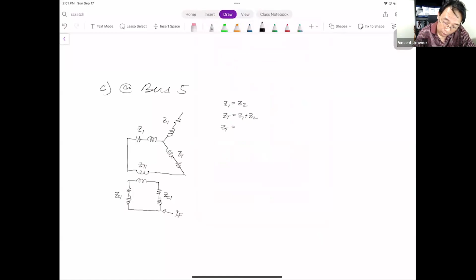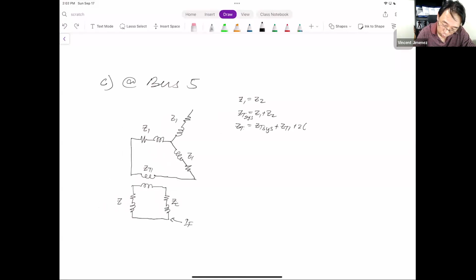Base naman sa formula natin, if there's a three-phase line-to-line fault, ang involved ay Z1 at Z2. Okay? So, we need to get Z1 and Z2. Z1 is equal to Z2. Okay, therefore, Z total is equal to Z1 plus Z2. Okay, so ZT is equal to your Z1 system. Okay, Z total is Z1 plus Z2 para sa system. Okay, and then the Z total is Z1 ng system plus the ZT1 or the impedance of your single phase transformer plus twice of C2 na yan, ano? ZC2. Cable number 2, which is also the same as your cable number 1.